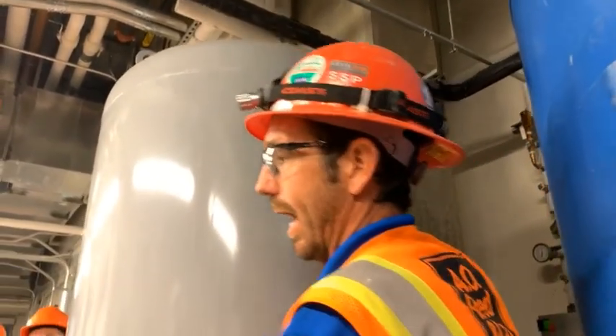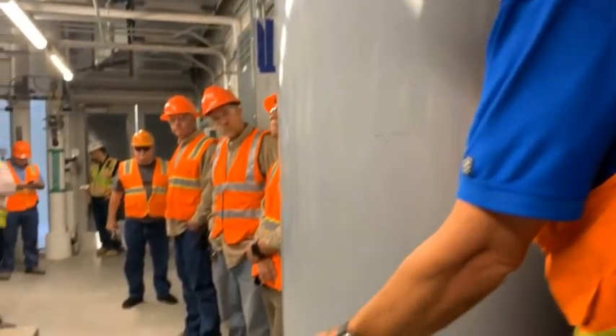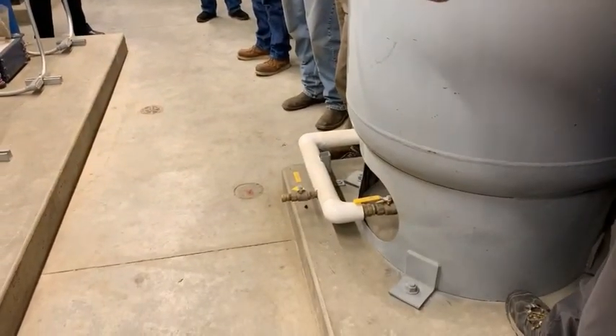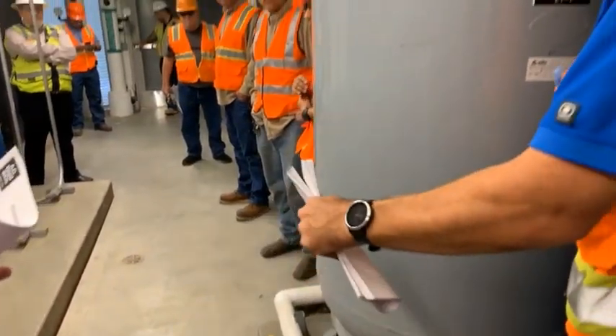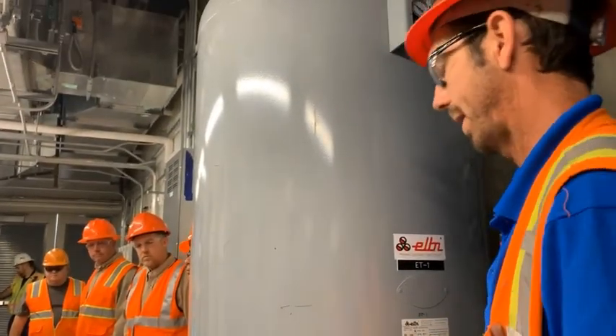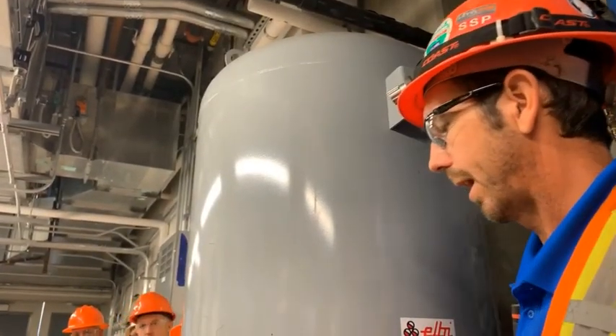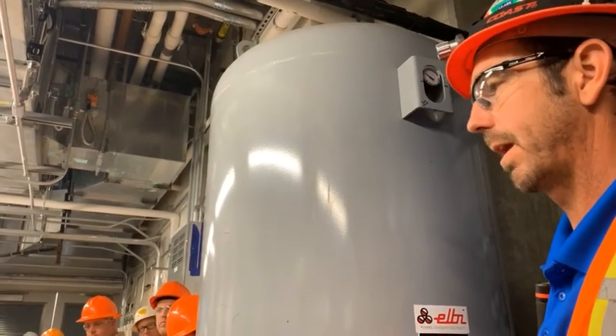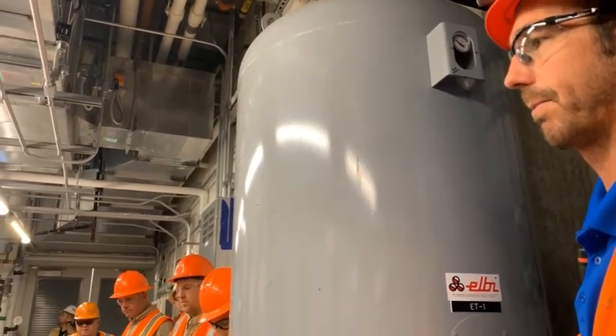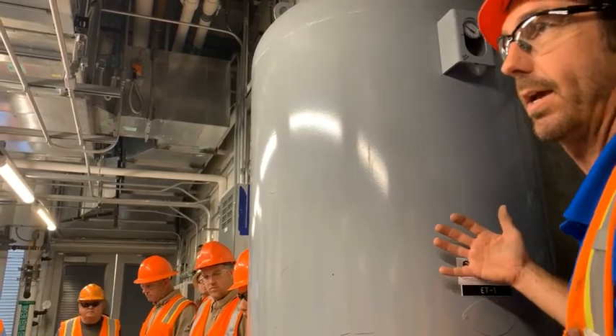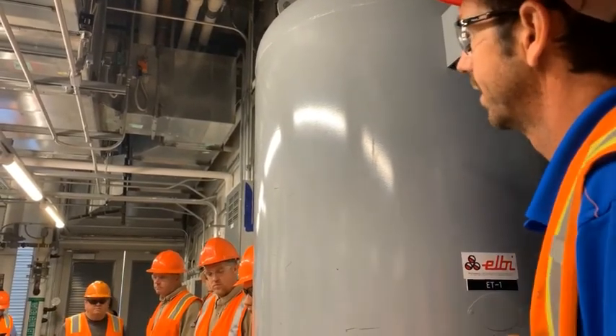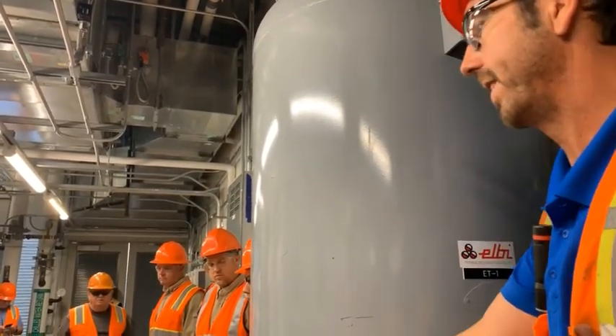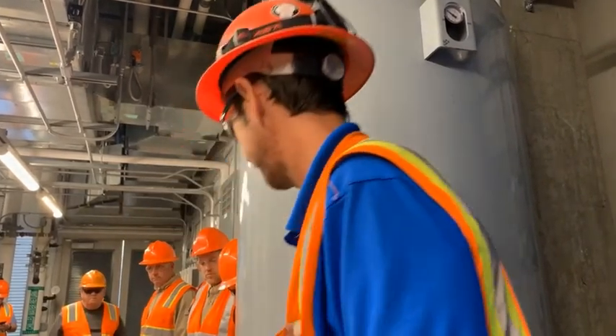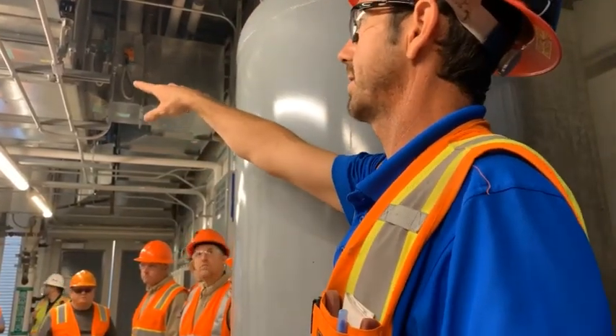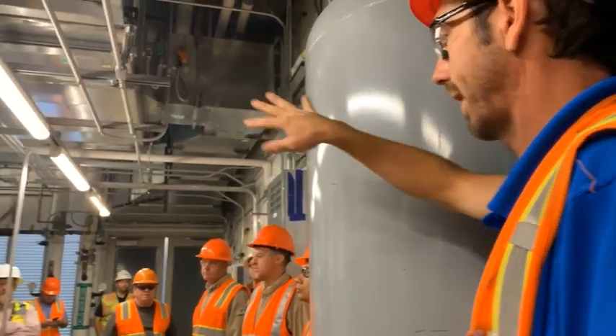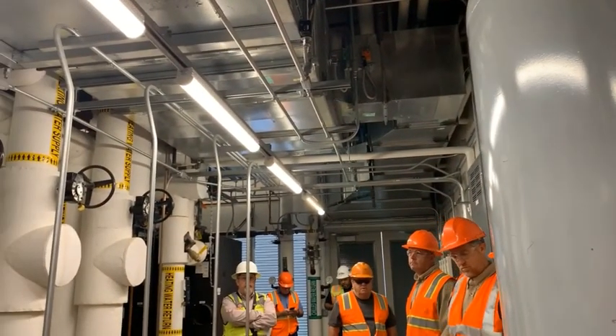When you're reading the pressure, I like to always just keep the drain hose open, or if you know it's all the way drained, take the hose off. Sometimes if the hose gets kinked or something, it might be able to hold a little bit of pressure in there. Just make sure that you have a bucket under there. I mean, it should be done bleeding, but in case the charge was low and you had to recharge it and there's still a little bit of water in the tank, you'd push the water into the bucket. The most important part is just make sure that this valve here, the drain valve, is open. Again, at this time, the isolation valve at the top of the system is still off, okay, because we're checking the charge on it, okay?